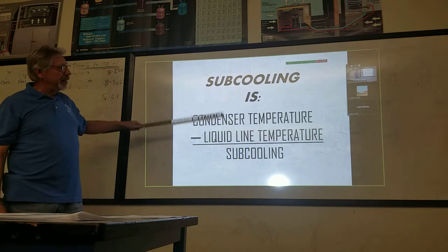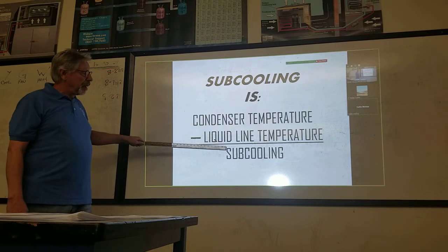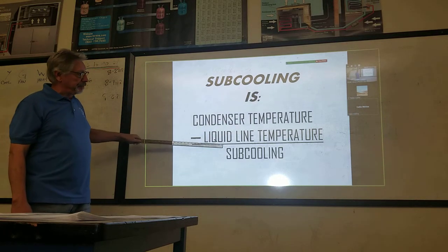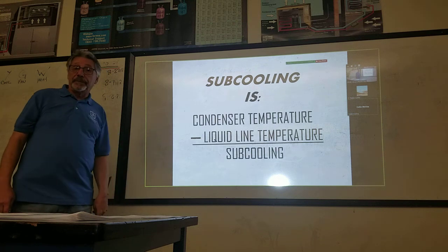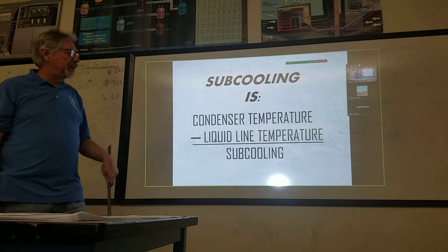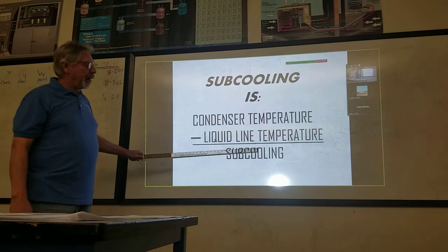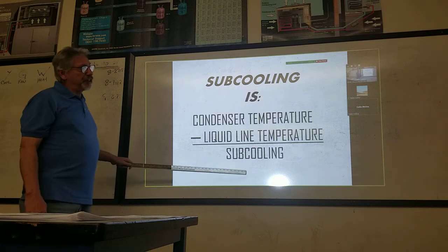Okay, subcooling is the condenser temperature, which is the saturation temperature, minus the liquid line temperature. So we're gonna take the temperature of the liquid line coming out of the condenser and find out how much subcooling.